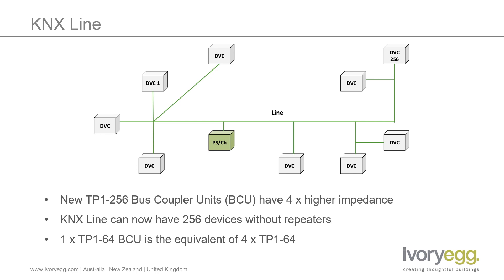To put it another way, there can be four times as many devices on a line while still maintaining the integrity of the telegram. The different types of bus coupler — the old ones and the new ones — are completely interchangeable, and using the newer version in the existing topology presents no issues at all. However, the sheer majority of KNX devices in the market are now using the newer version, so we can start promoting a line as having 256 devices without any line repeaters. This massively simplifies the installation and realises the true potential of the KNX topology.